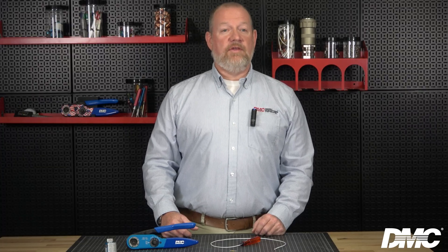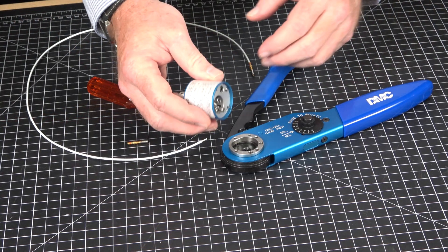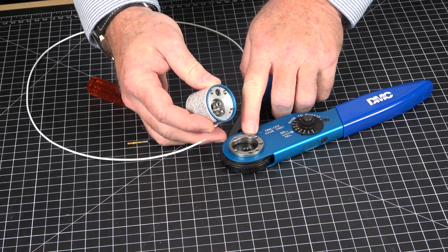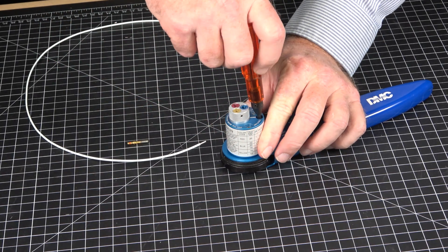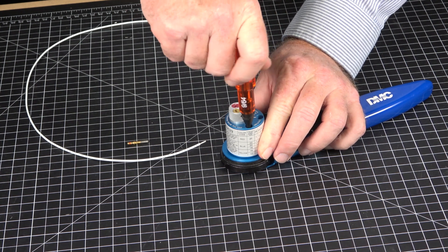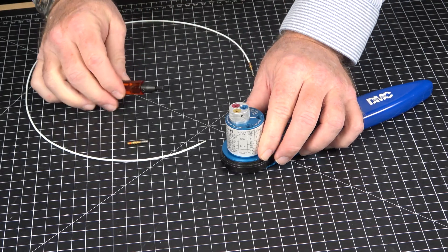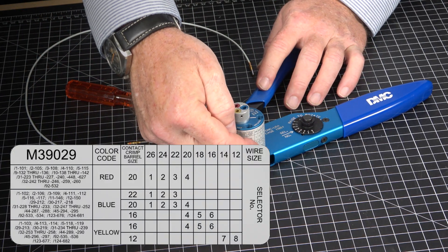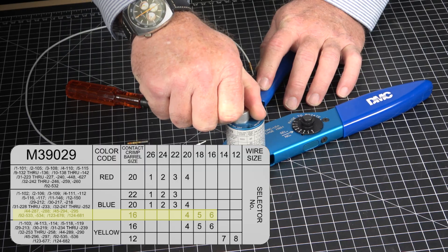Now that the tool has passed the go/no-go test, install the compatible accessory. In this example, we will install the TH1A turret head onto the AF8 crimp tool. It is essential to keep the handle open throughout the process. Start by aligning the guide pin with the small hole in the retaining ring, then screw in the turret with the 9/64 hex wrench. Using the data plate, identify part number M39029/32-247 and rotate the turret until the color-coded insert is in line with the index mark.